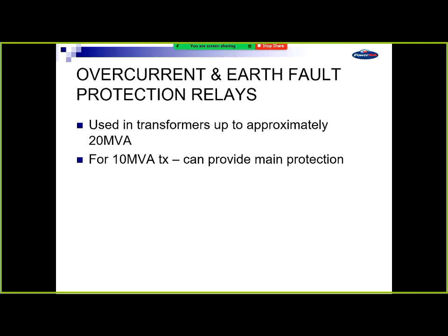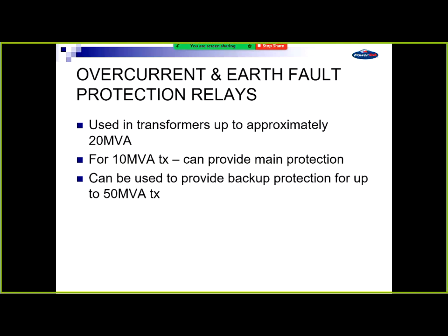For 10 MVA, they used to be the main protection, and you can use them up to 20 MVA. They can also be used for backup, for higher voltage, higher rated transformers. For us, we sometimes use them as a backup, but we've got the one IED. With the modern relays, you can do many things internally in them. So sometimes if we need to back up, not so much for us, but someone else asks us to back up their network, especially Ergon at 66 kV.